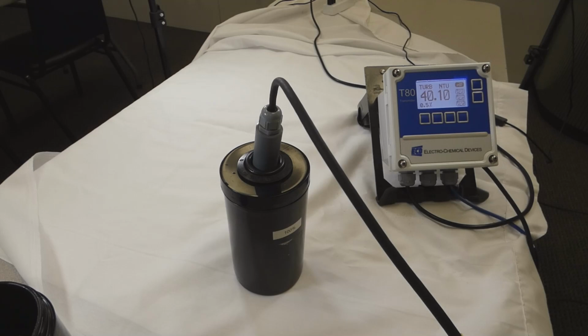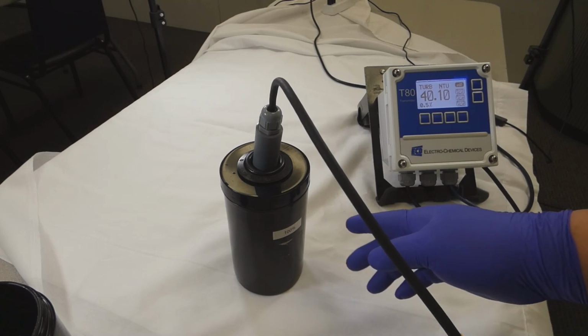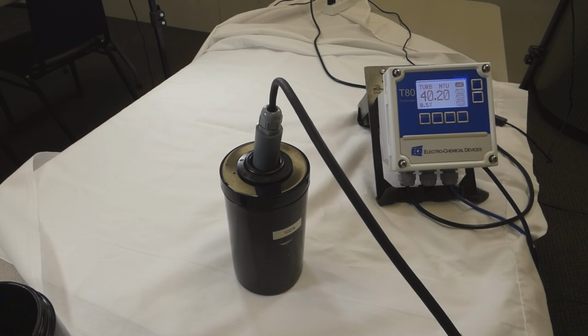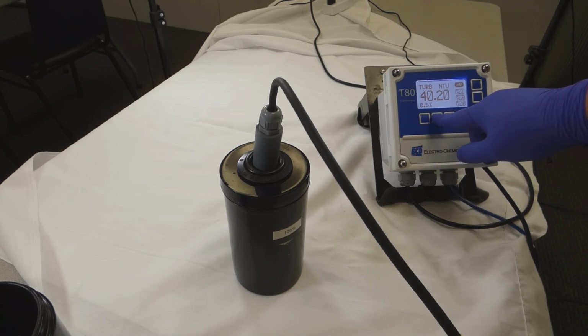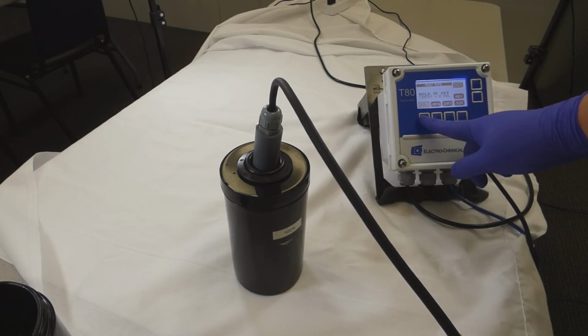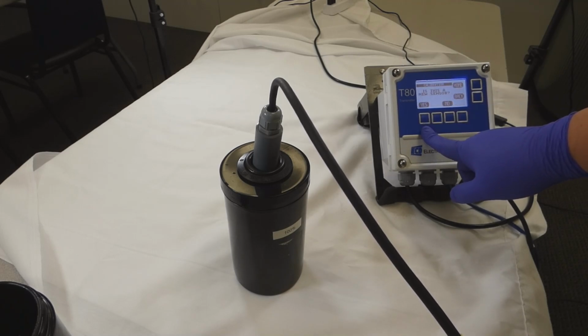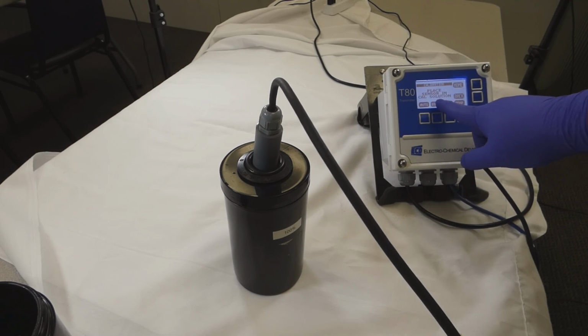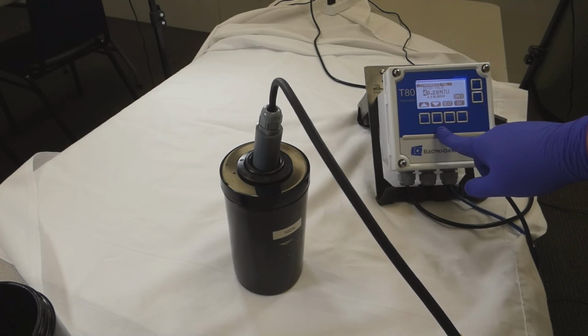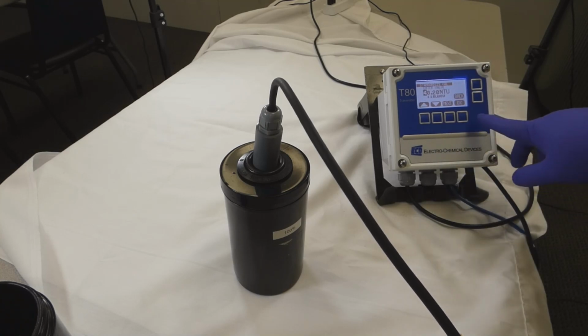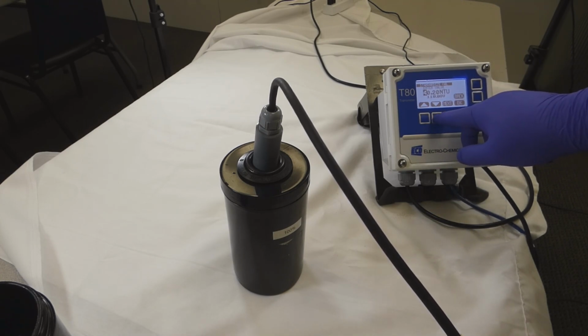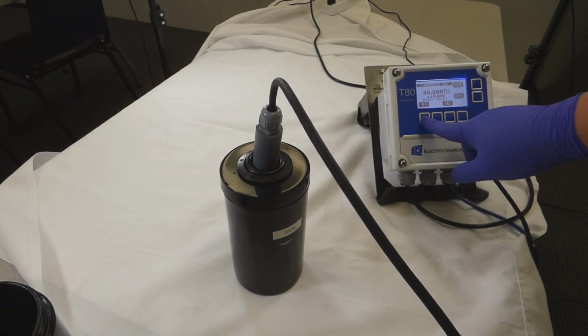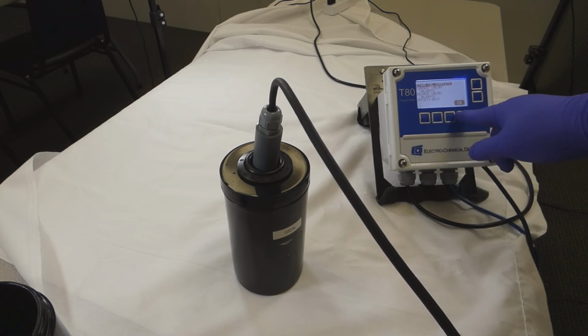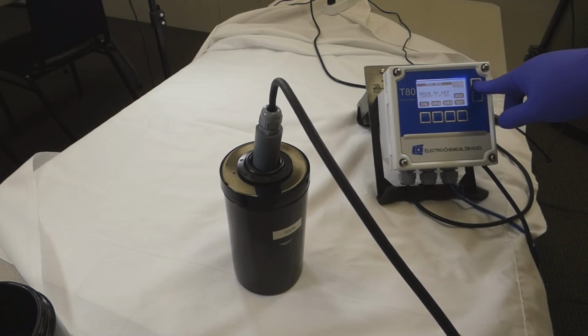In order to do a standardization, you will need to put the solution that you wish for. This time you can press any of the bottom 4 keys twice. Press Cal. Is this a new sensor? Say no. Do stand for standardization and enter in the value that you wish for. Once you are done, you'll press OK. Accept this value, say yes, OK, home, exit.